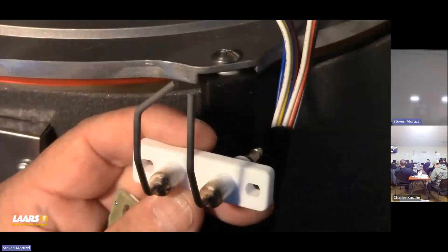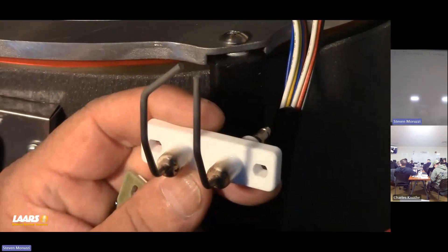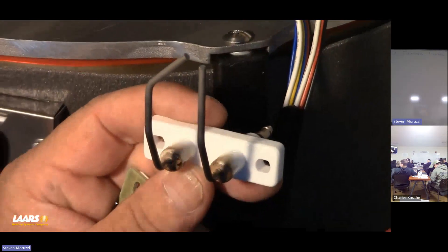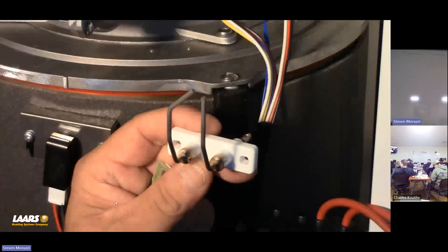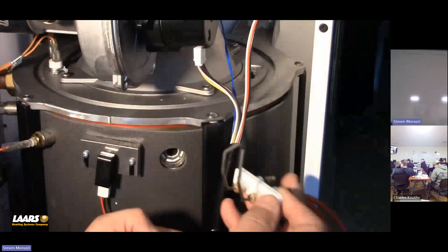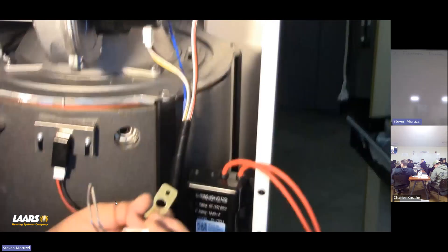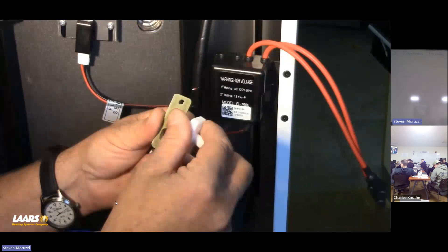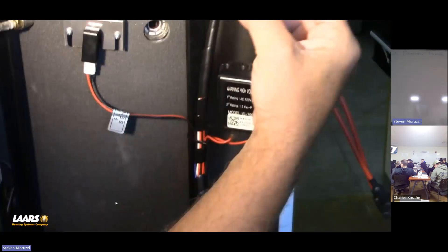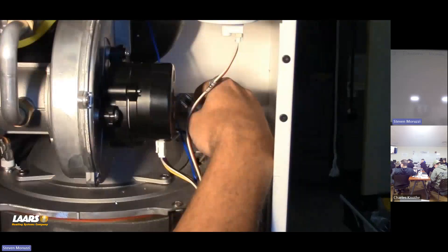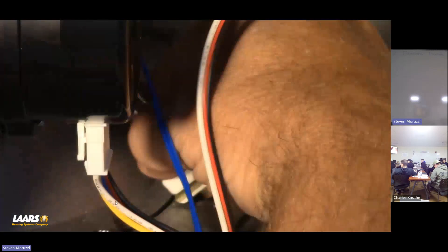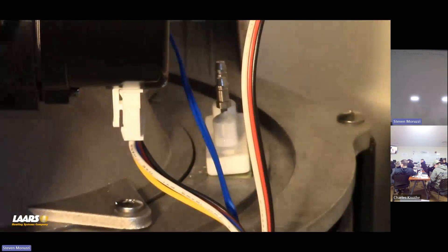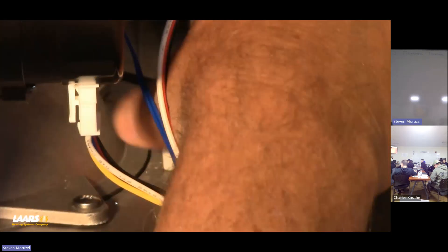Gen 1 had that igniter here on the right side. Gen 2 is on the back. What we found was during light-off for propane, high altitude, and everywhere else, we were having rough light-offs or ignition trials and error code 11. They found it to be smoother light-off on the back. So that was relocated to the back. That has to do with the way that the burner itself was manufactured.